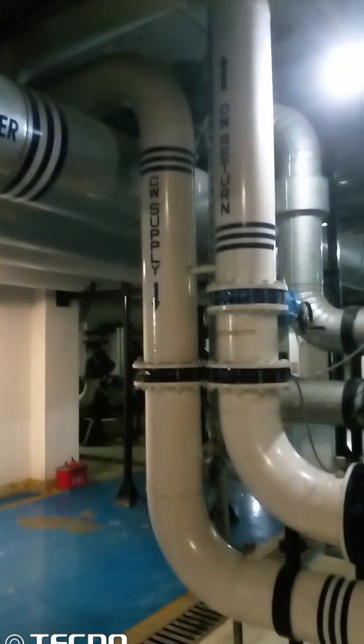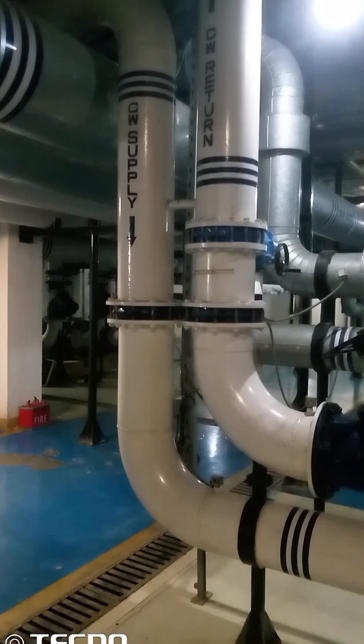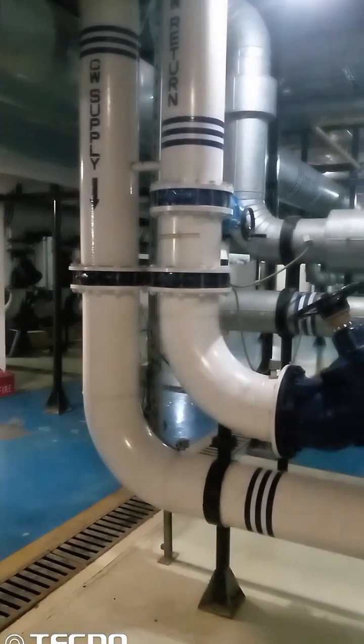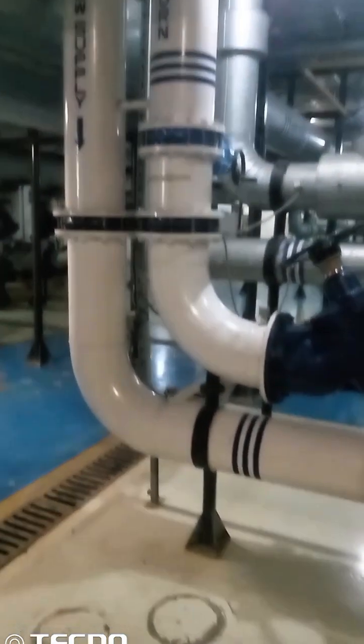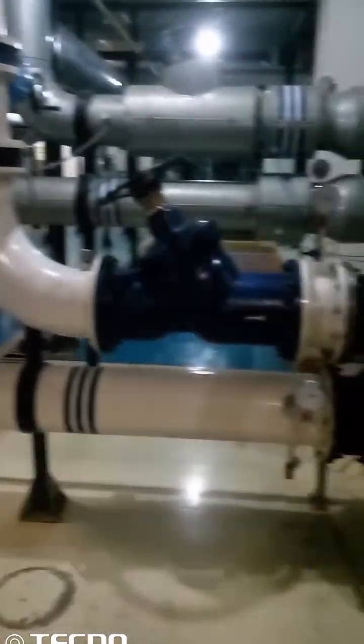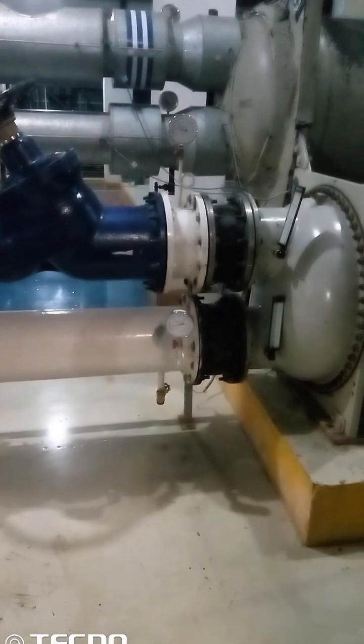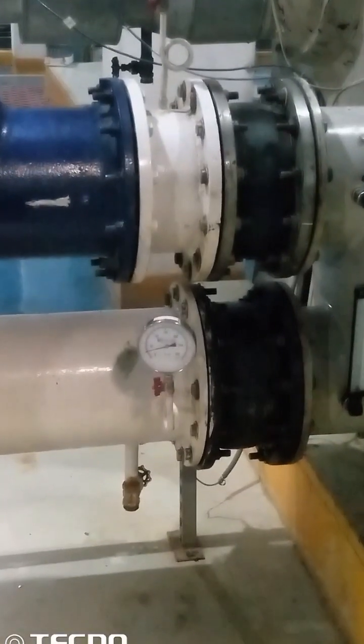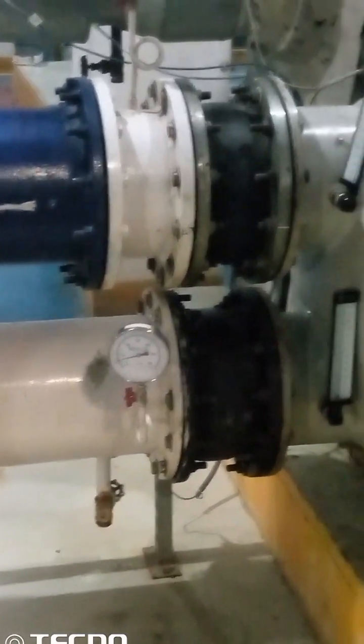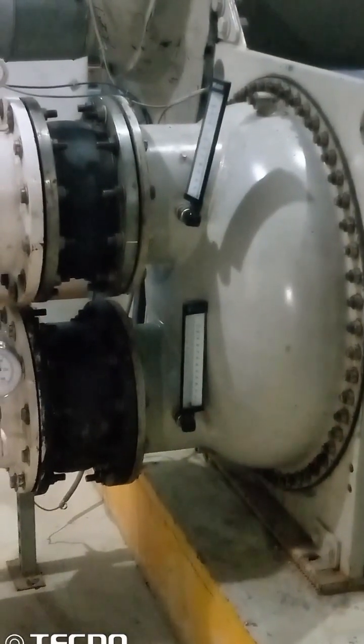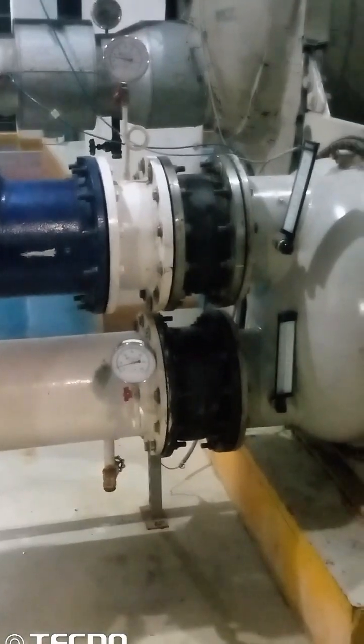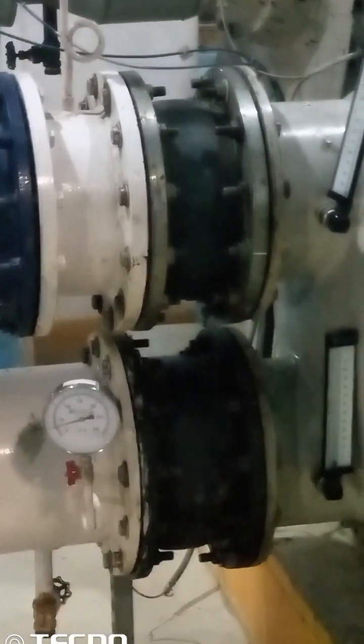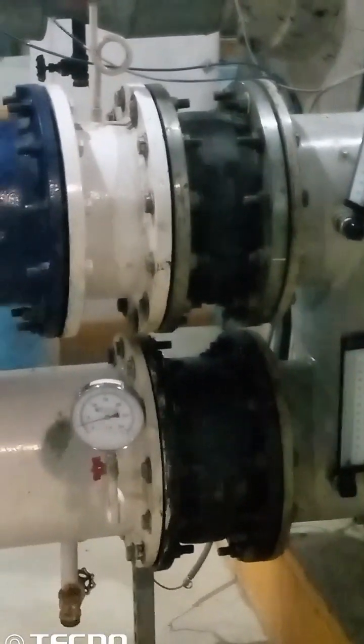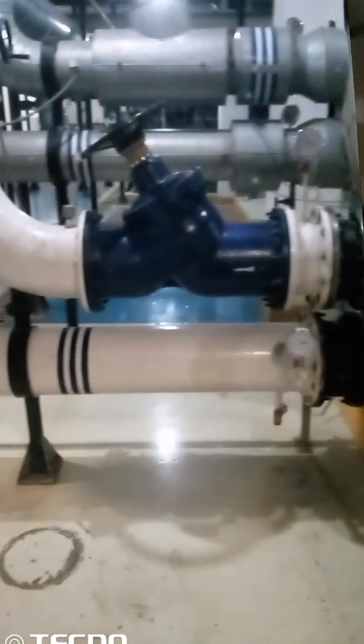Over here are the supply and return lines from the cooling tower to the condenser of the chiller, the condenser water return and the condenser water supply. And one thing to keep in mind is that the balancing valve is always installed on the return line. Moreover, there are pressure gauges and temperature gauges for the delta P and the delta T, the pressure difference and the temperature difference between the inlet and the outlet of the condenser, with a flexible connector installed at the start for the purpose of vibration isolation.